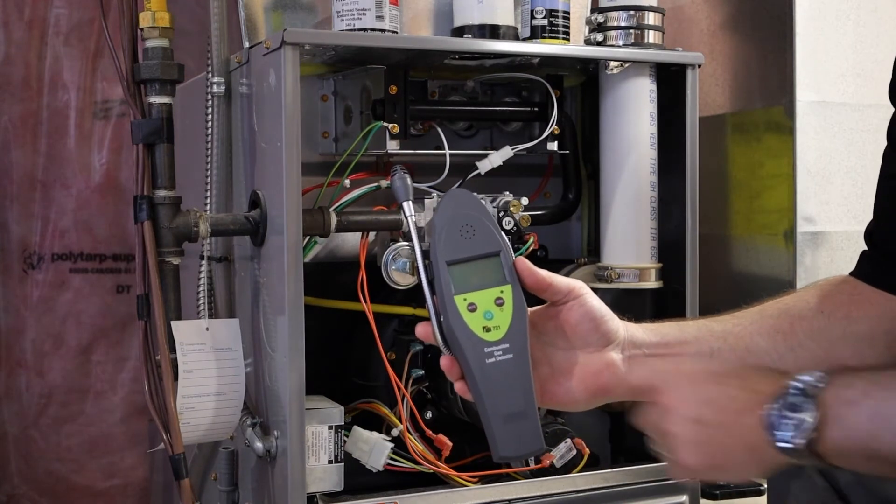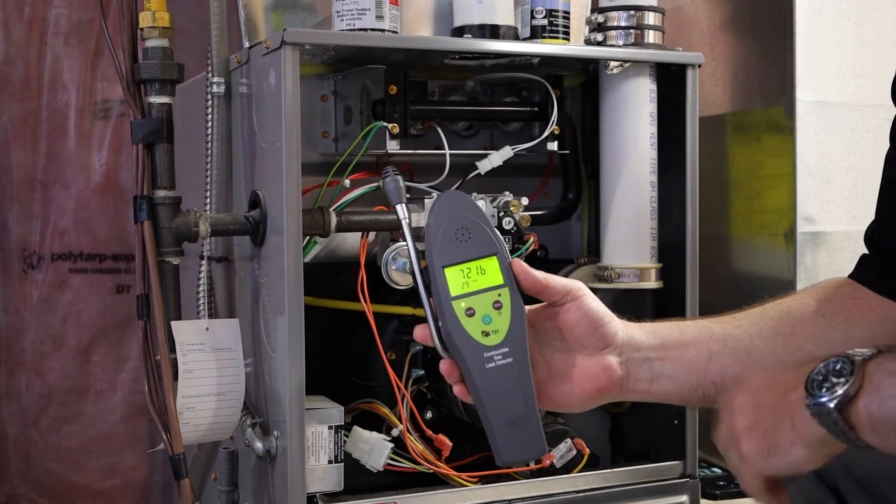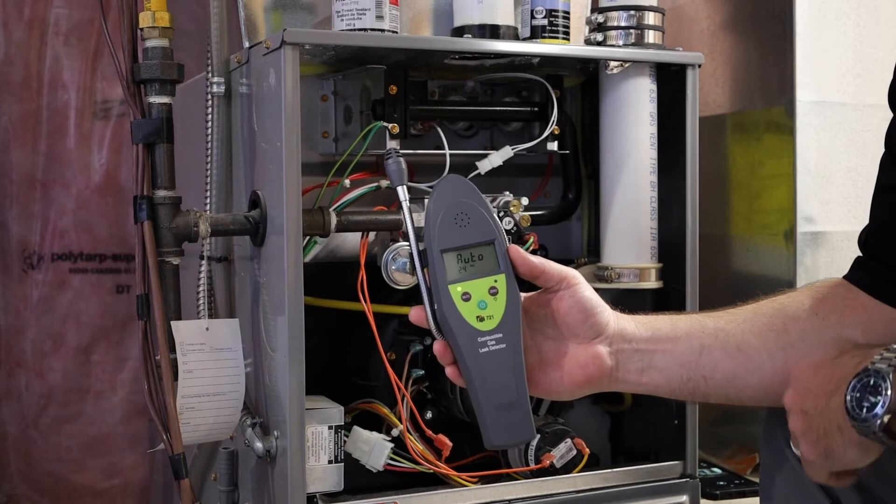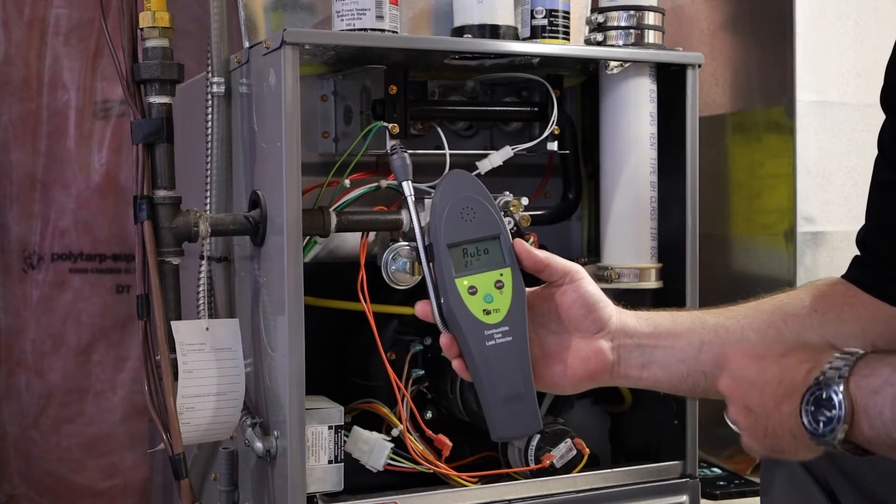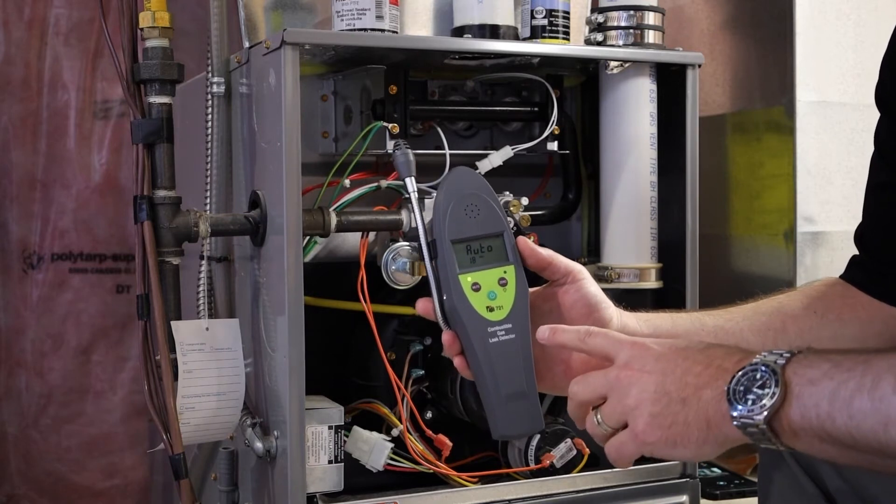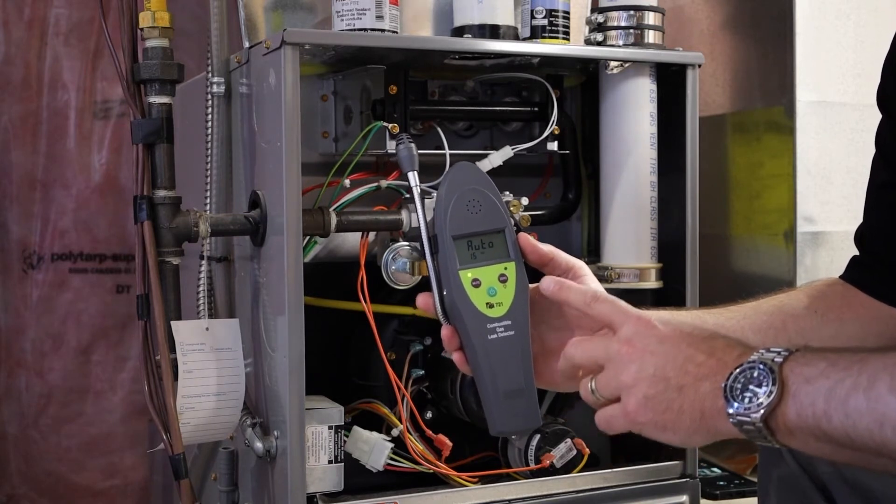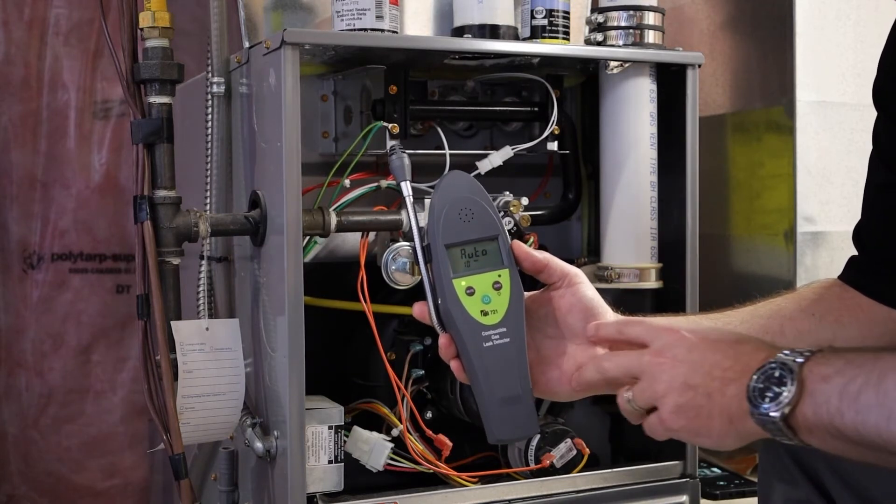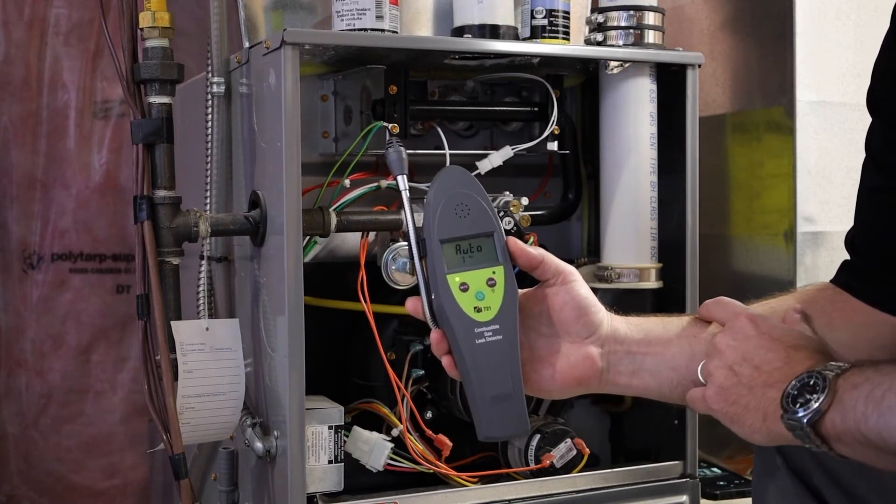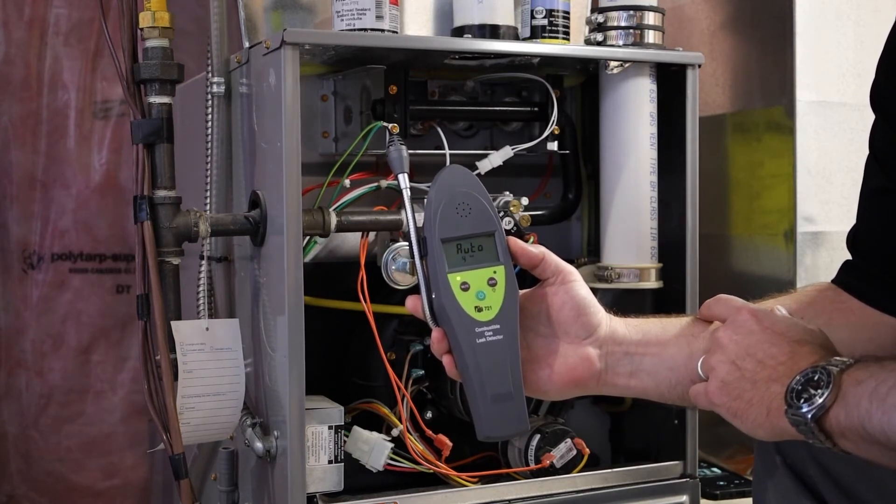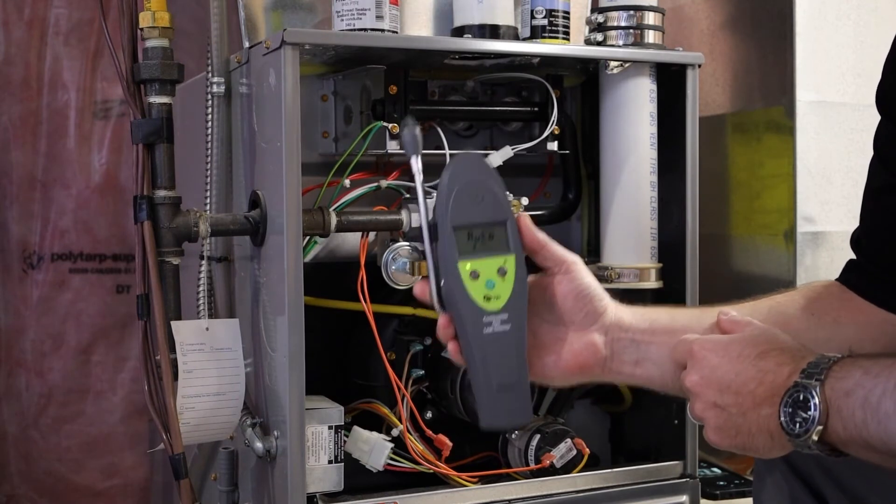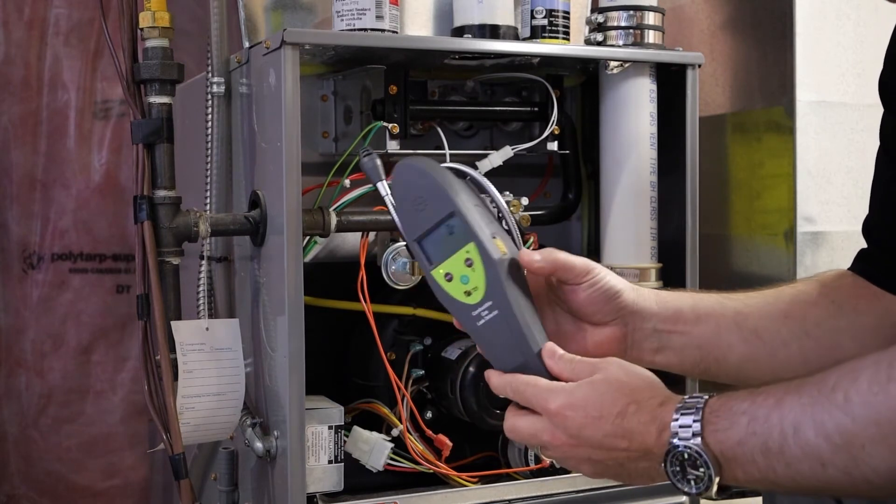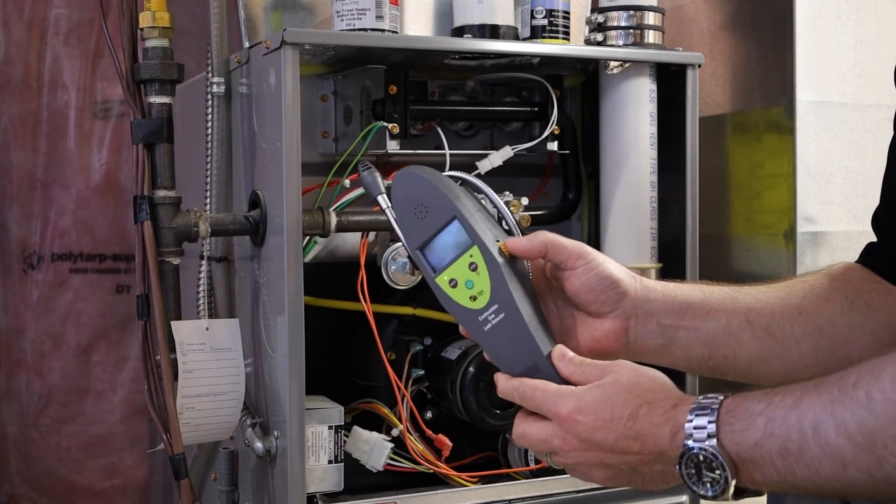Here is the 721. Does all the combustible gases. But now we've gone into a LCD display. This one will actually display how big the leak is. It will also do LEL, lower explosive limit. So it will display in percent LEL. I'm waiting for my 30 second countdown to be done. Could take longer if the ambient temperature is really cold. Good set of batteries helps too. It's got the adjustable tick rate on the side so you can tune it.